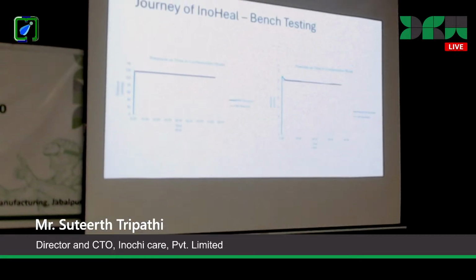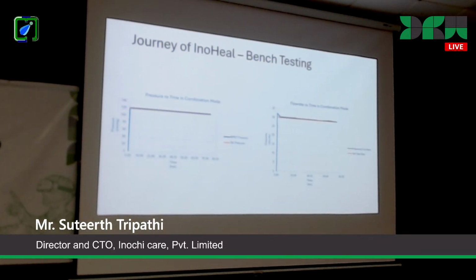As you can see, the orange line represents the set pressure, the desired pressure we wanted the device to operate on. The blue line on top is the actual NPWT pressure that our device was able to create on the sample wound bed. These pressures are almost identical, with negligible variation between them, and no variation throughout the entire duration of the cycle, that is, throughout the 3 days. There is no difference between the pressure we wanted to provide and what the device actually provided. This gives us confidence that our device is ready to provide this kind of pressure to the patient, because there are no variations and no failures.